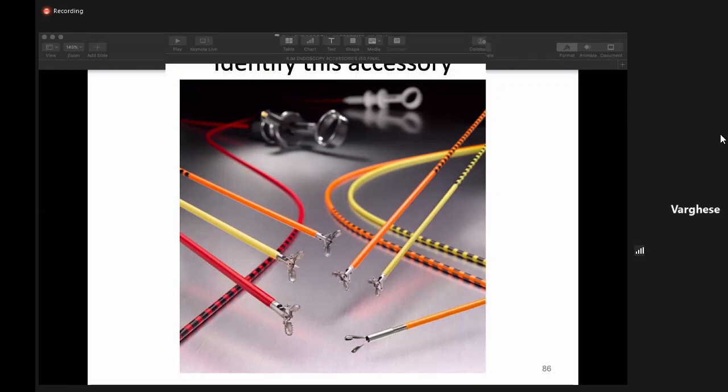Okay. Now, how do you know whether your biopsy forceps is really going to open inside when you put it inside? Can you do an external test? Yes, sir. I will check it first. It's opening. You ask your assistant to open it. And when you take it inside, it is not opening. Yes. So this happens after repeated reuse.